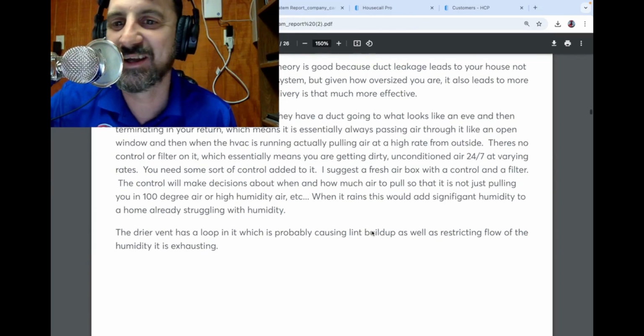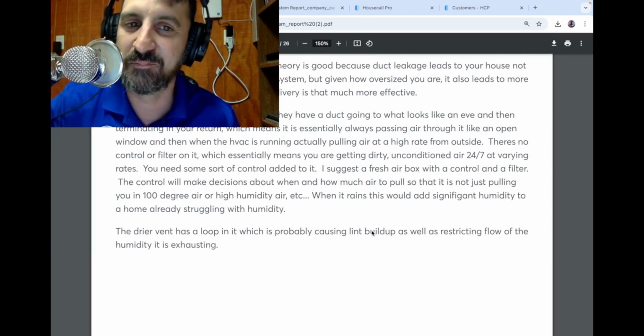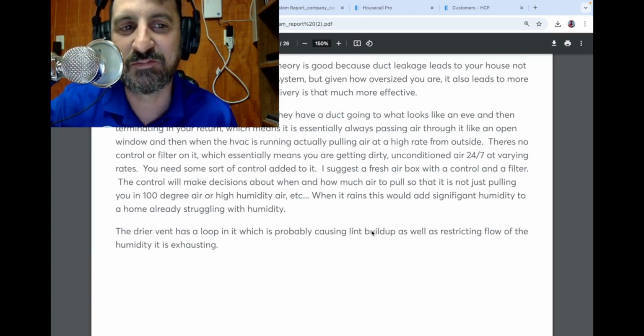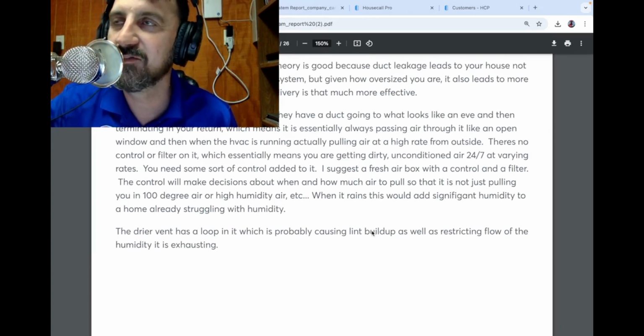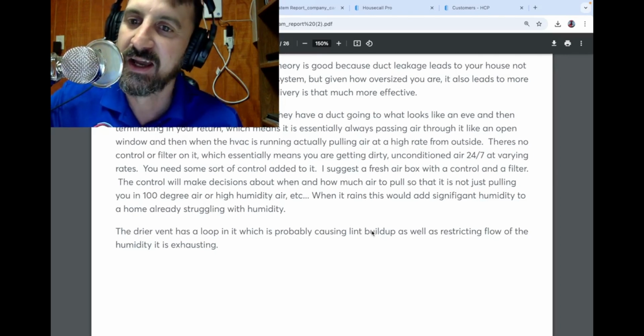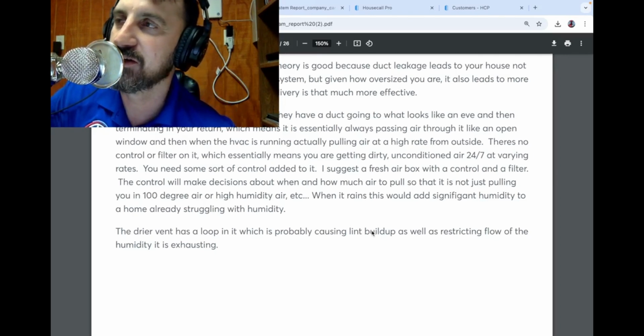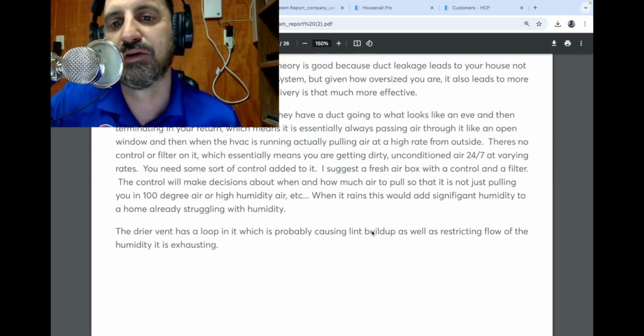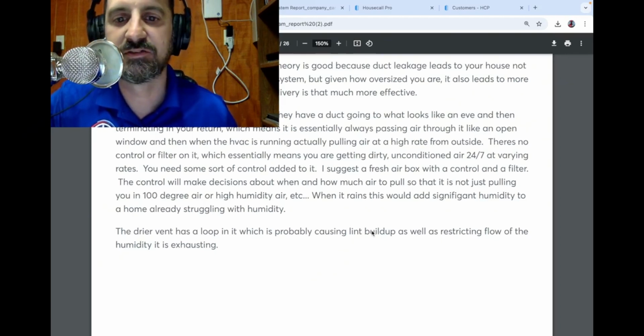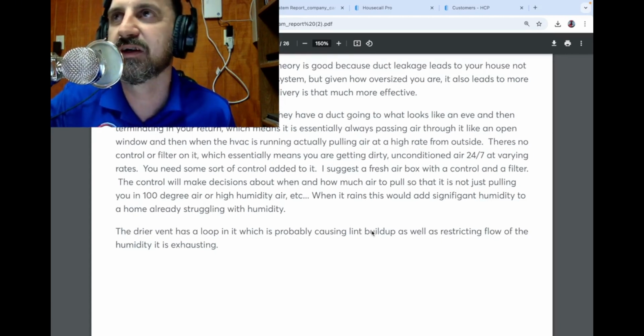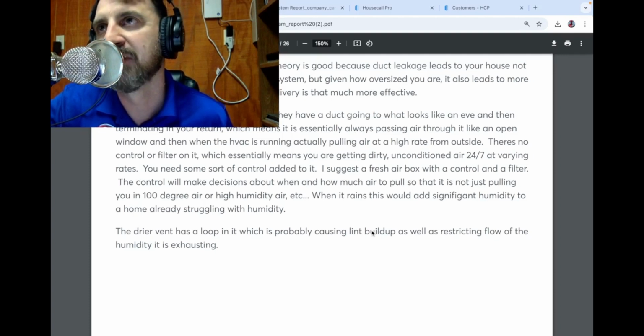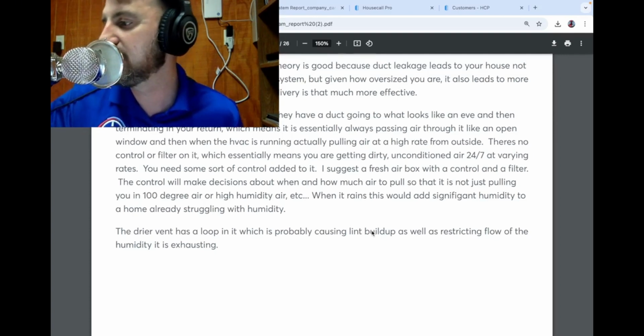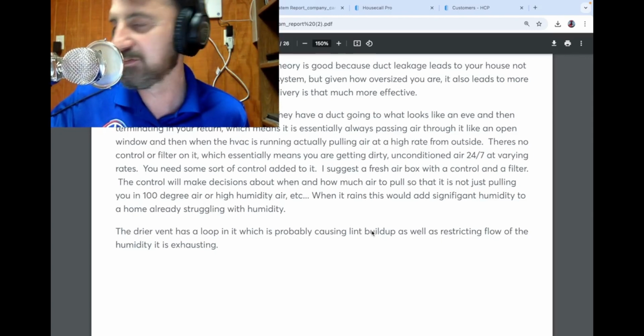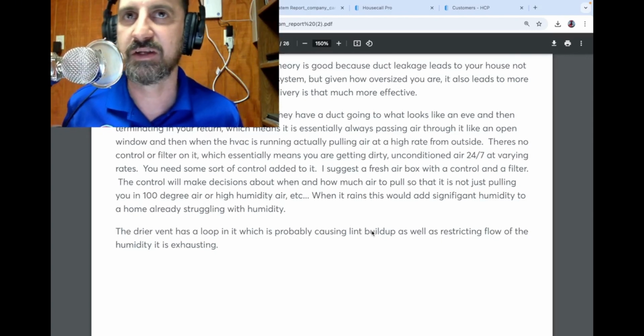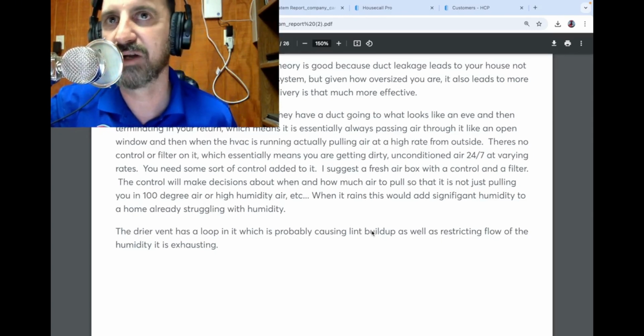The fresh air intake is done incorrect. They have a duct going to, I believe, an eave, where that eave is cut for some ventilation. And then it terminates straight to the return. No damper, no timer, no filter, nothing. It's just straight air from outside, regardless of what the outside is doing. When the unit is off, this is the equivalent of having a window open, basically like having a window open about a half an inch, about a foot wide.